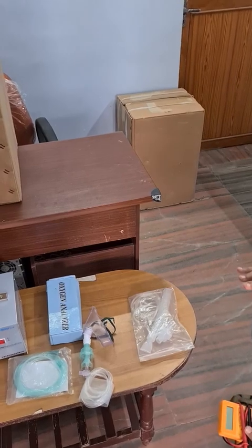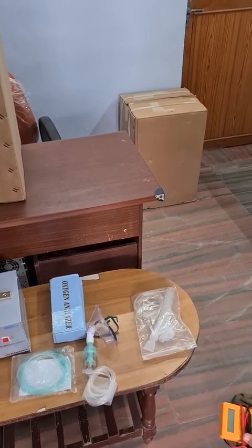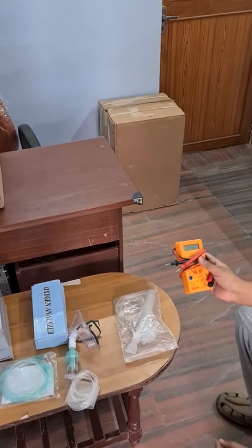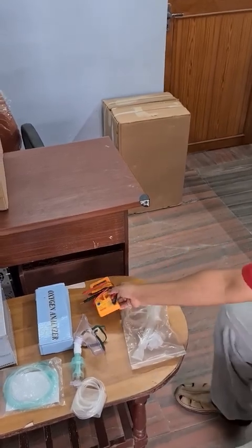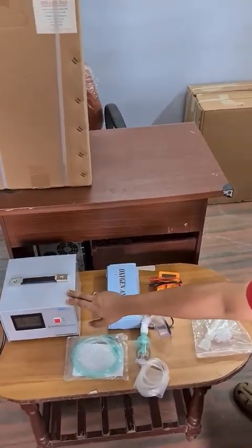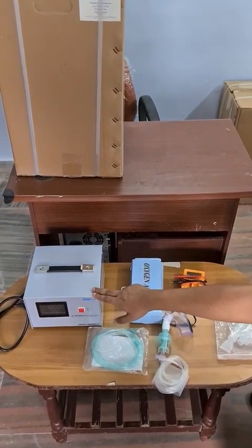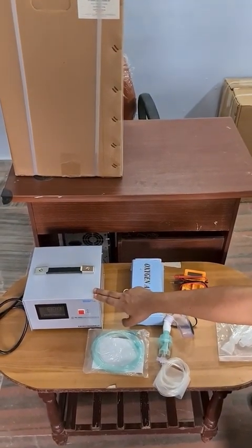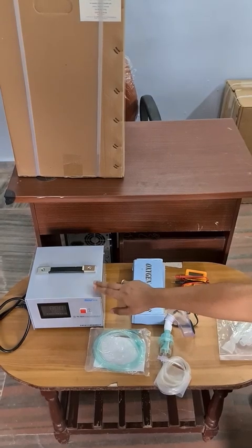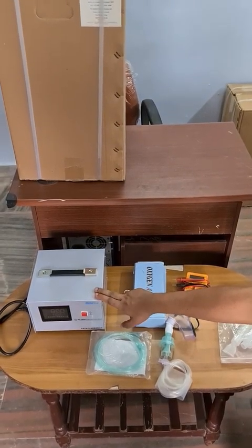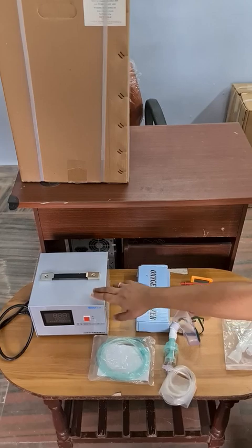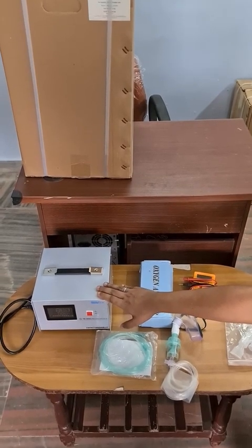If the voltage is more, for example 240 or 245 plus, then you will need to buy a stabilizer. And you can see here, this is a high grade medical stabilizer, a medical grade servo stabilizer. The reason for using a servo stabilizer is that even if the voltage shoots up to 260, it has the capacity to bring it to 220 or 230.